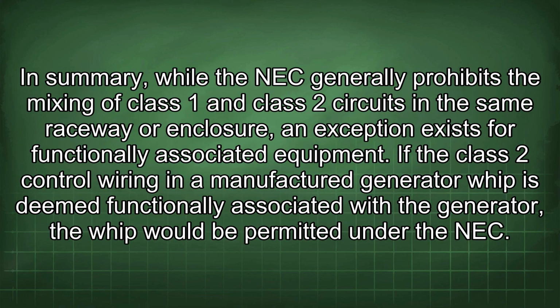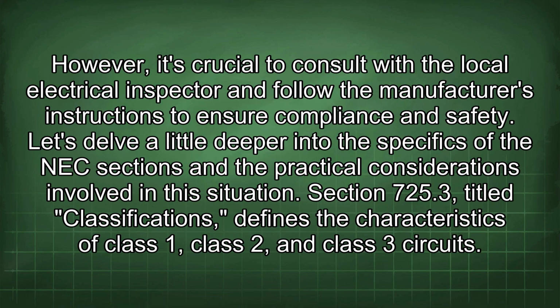In summary, while the NEC generally prohibits the mixing of Class 1 and Class 2 circuits in the same raceway or enclosure, an exception exists for functionally associated equipment. If the Class 2 control wiring in a manufactured generator whip is deemed functionally associated with the generator, the whip would be permitted under the NEC. However, it's crucial to consult with a local electrical inspector and follow the manufacturer's instructions to ensure compliance and safety.